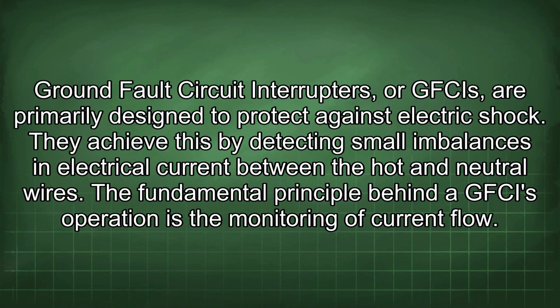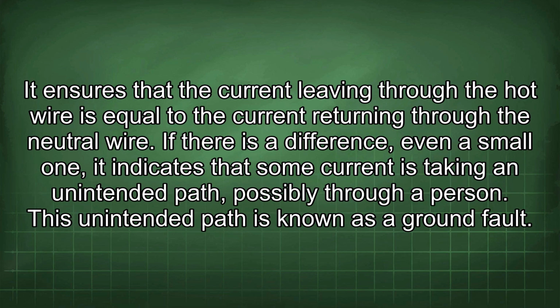Ground fault circuit interrupters, or GFCIs, are primarily designed to protect against electric shock. They achieve this by detecting small imbalances in electrical current between the hot and neutral wires. The fundamental principle behind a GFCI's operation is the monitoring of current flow. It ensures that the current leaving through the hot wire is equal to the current returning through the neutral wire.